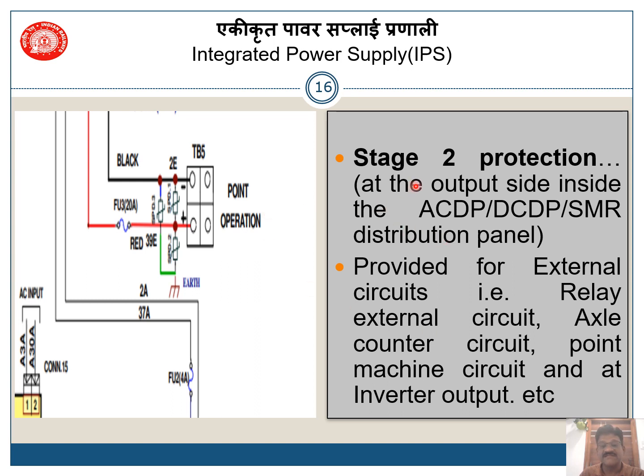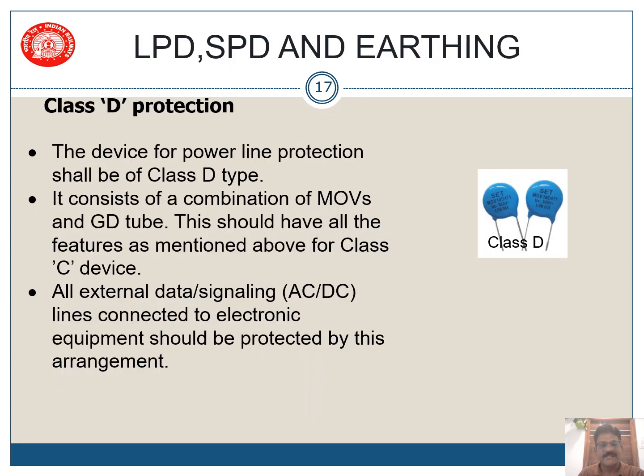This is the second stage of protection, that is point operation supply. Your supply is going outside, so there we need to provide protection here. Here you can see class C protection is provided. One SPD is provided between positive and negative. The second SPD is provided between positive and earth, while the third one is provided between negative and earth. So generally it is a must that three SPDs are used for each power supply that is connected to the outside world. This is the class D protection. Nowadays, these MOVs are generally replaced with the class C protection only.